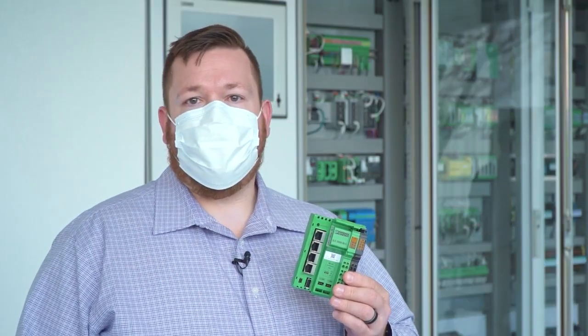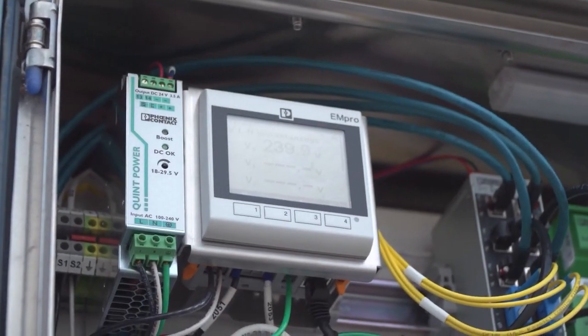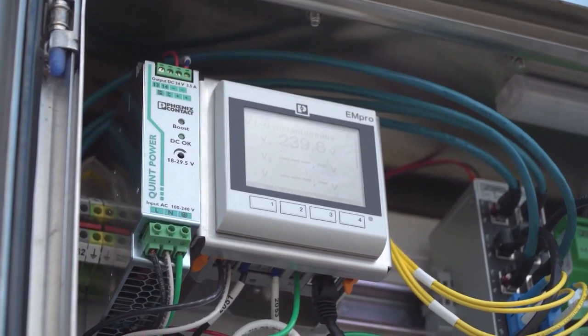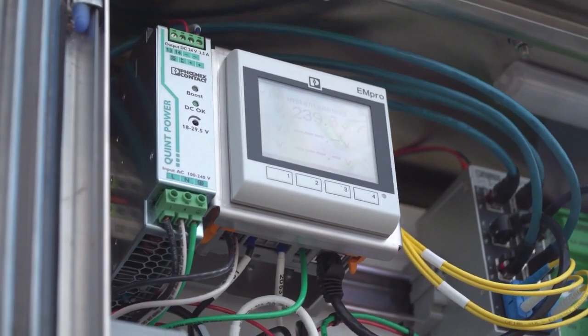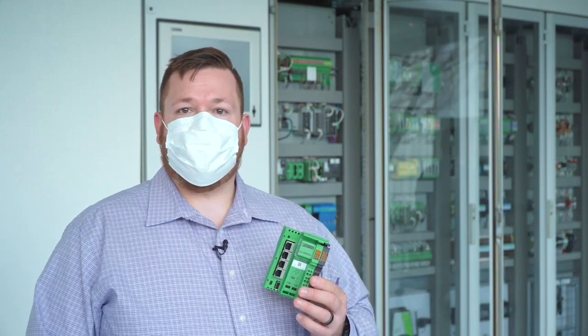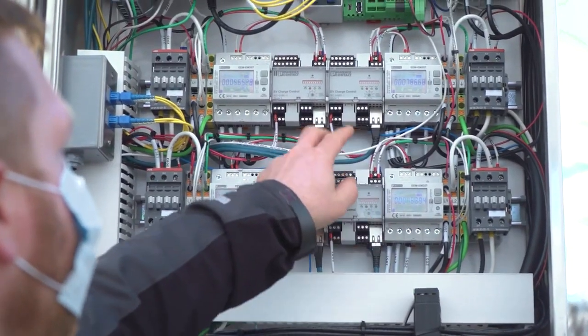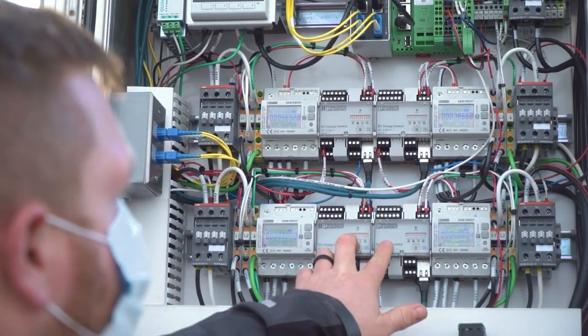We also added a new EM Pro power meter. All these power meters communicate back to the ILC 2050 via the Modbus network. And lastly, we added temperature sensors to the cabinet so we could see what kind of temperature ranges the ILC 2050 experienced in the outside cabinet.